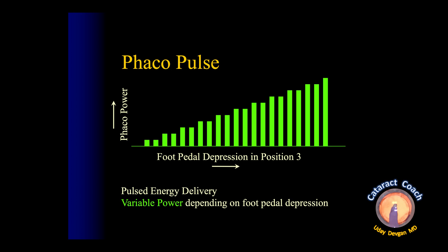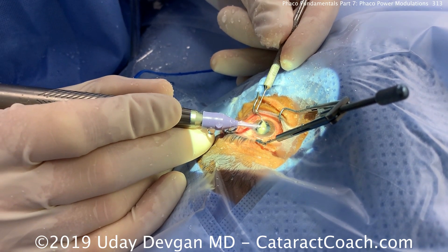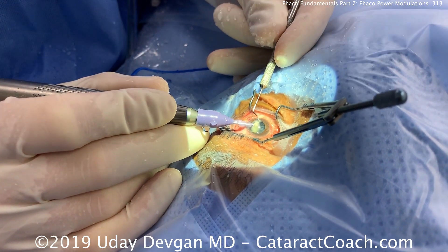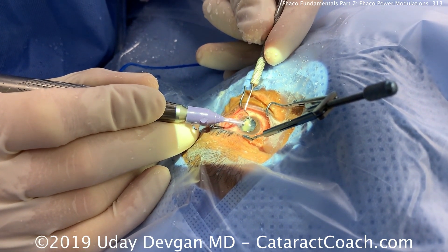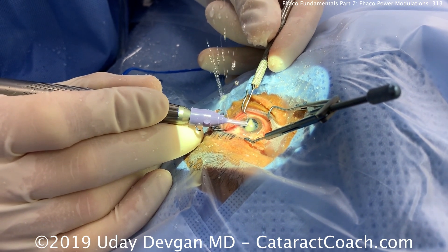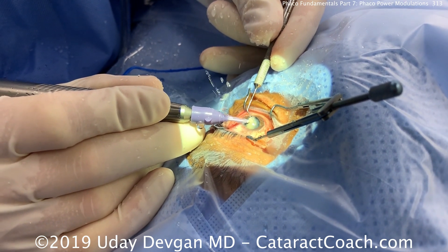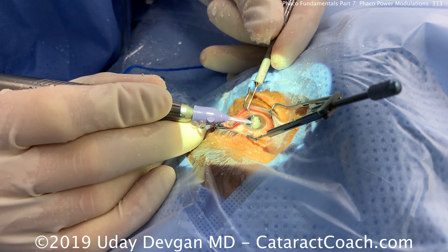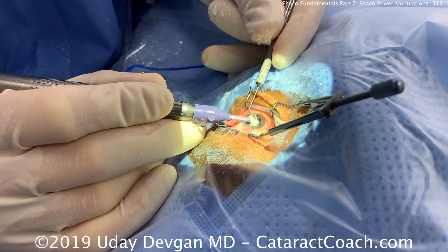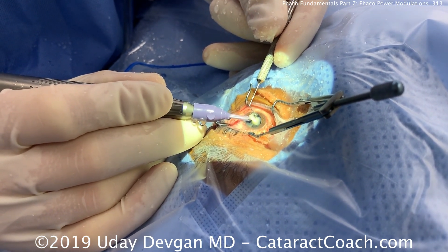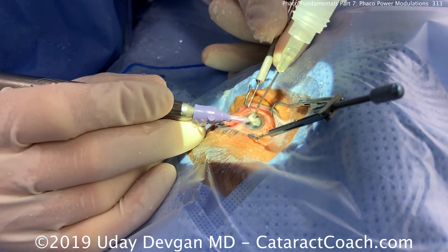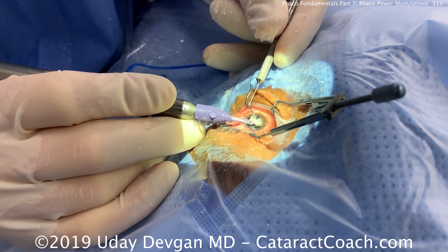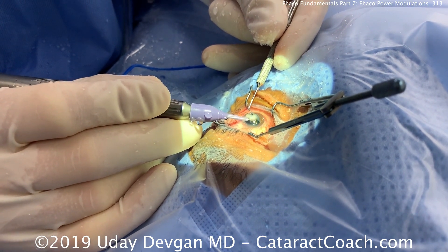Pulse mode works on the same concept — stepping deeper on the pedal delivers more energy — but the power is delivered in discrete pulses with rest periods between them. This allows cooling of the phaco tip. You can have a very wide range of pulse rates, from just a few pulses per second up to a hundred or more per second. Interspacing energy with cooling prevents heat buildup on the tip and can also increase followability of nuclear pieces.